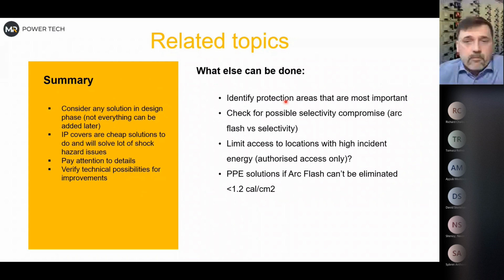Sometimes, and actually very often, we check for the possibility between selective operation and arc flash safety. As a simple explanation, sometimes it's hard to make things selective, but we make it better from the arc flash point of view, much faster. And once the customer is aware of it, he might accept it and live with this, I would say, until the next improvements.